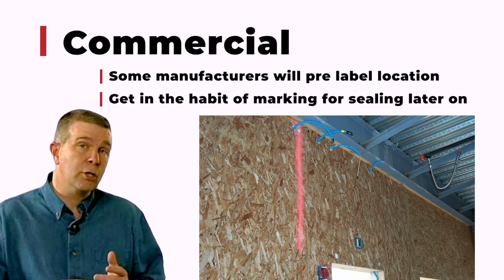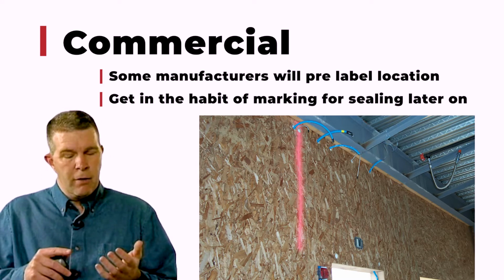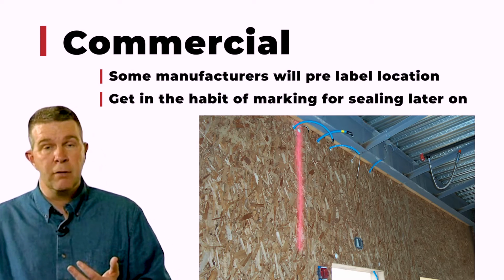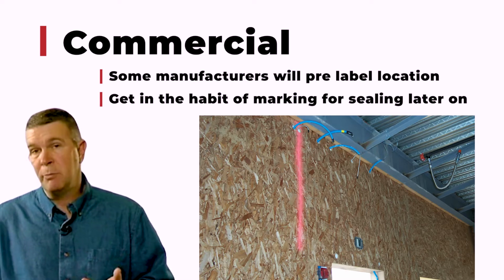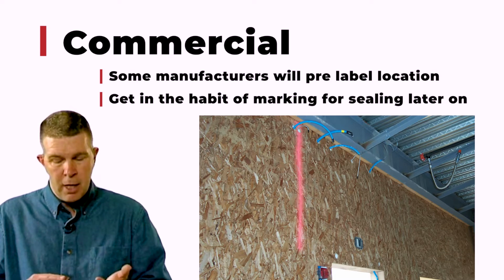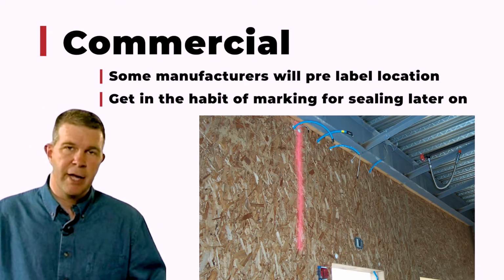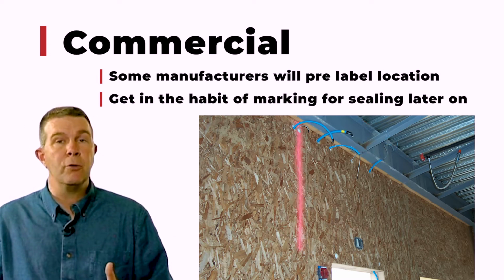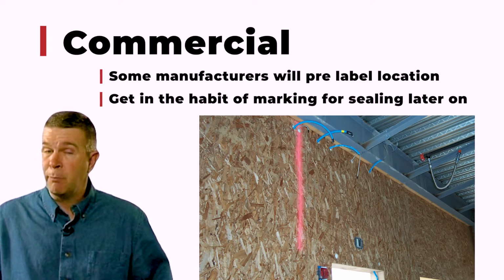Now, if we get into the commercial world, things change a little bit. Once we get into the commercial world, the majority of the times, we find that the electrician doesn't have the luxury of just pulling a Romex wire. It needs to be shielded in some way, or it needs to be in conduit, and that can add a level of complexity. The first thing we typically do is we increase the size of the chase. Instead of a standard 1.5-inch chase, we may bump that up to 2. Why? Because now we're dealing with a metal shielded or a Smurf tube, and that Smurf tube can be pushed through that chaseway if it's a little bit larger, just a little bit easier.